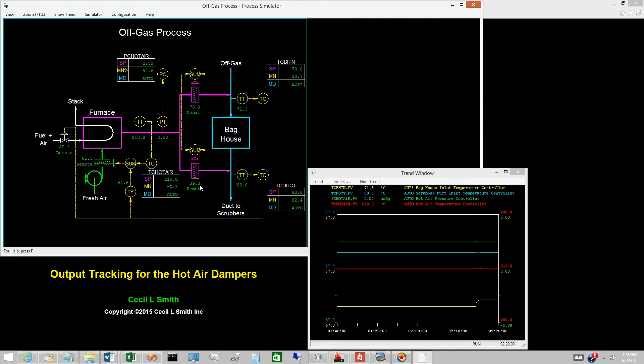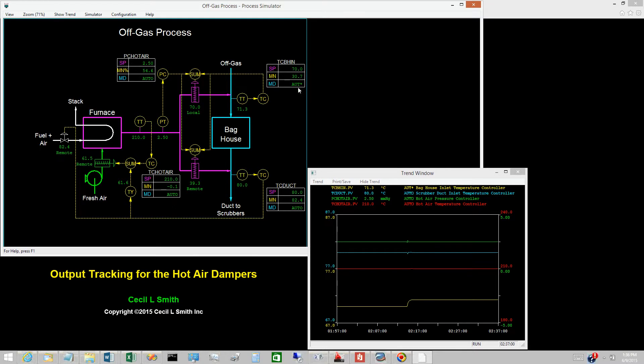Dampers are not linear, so the net effect of these two changes on the hot air pressure is not zero. The hot air pressure controller responds so as to maintain the hot air pressure at 2.5 millimeters of mercury. To maintain the hot air pressure at 2.5 millimeters of mercury, the opening of the hot air damper to scrubber duct inlet changes to 39.3%. The difference in damper openings is 30.7%, and the tracking logic forces the output of the baghouse inlet temperature controller to 30.7%. The baghouse inlet temperature has risen to 71.3 degrees, and as the set point is 70 degrees Celsius, this controller would normally be decreasing its output. But when tracking is active, the output remains at 30.7%.